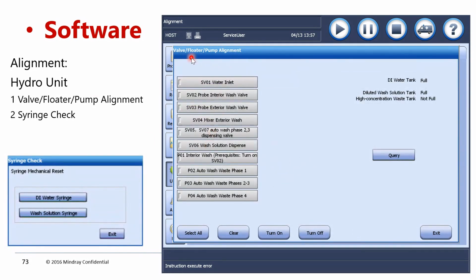So here is the floater pump alignment. So these are the valves we discussed. Up to 7 valves we have. Individually you can verify the valves and wash solution sensors and pumps. Okay, these are the float sensors: DI water tank sensor, wash tank sensor, detergent tank sensor, high concentrated waste sensor. You can verify whether each sensor is working or not, and here you can verify whether the pumps are working or not. Okay.